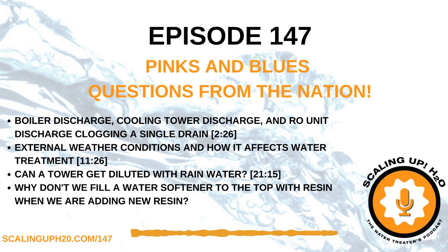But now we're talking about the phase change of a liquid to a gas. So this is evaporation. How do we get water to want to become a gas? And this term is called the latent heat of vaporization of water. Again, a very impressive term to share with your friends. And simply what this means is how many BTUs it takes to change water from a liquid to a gas. Now, the actual number is 970 BTUs. But us, as water treaters, we are very simple folk, and we round it up and we say 1,000 BTUs.